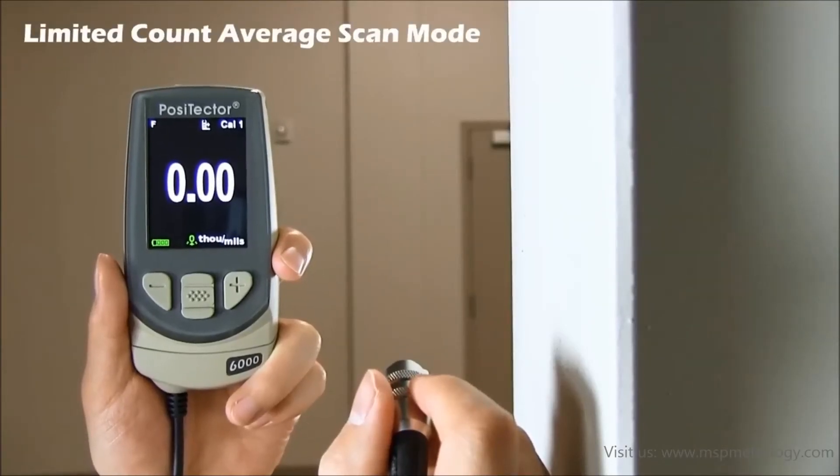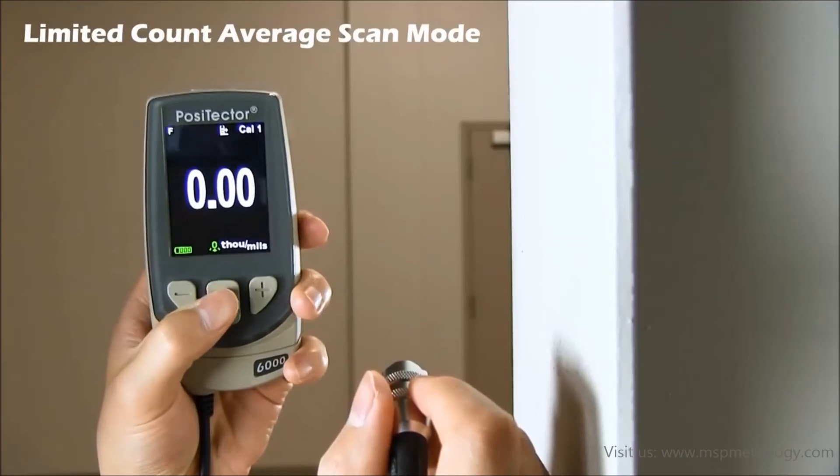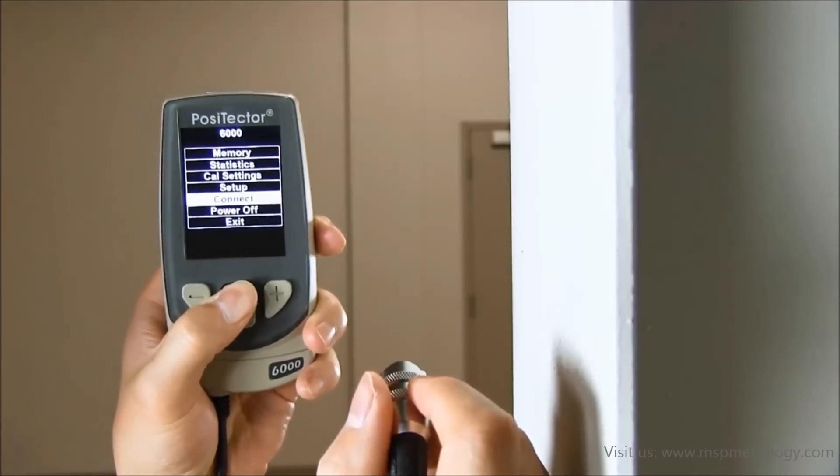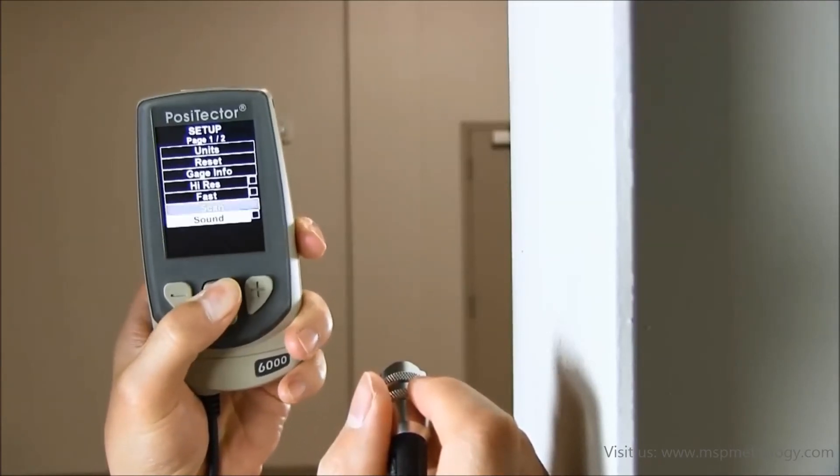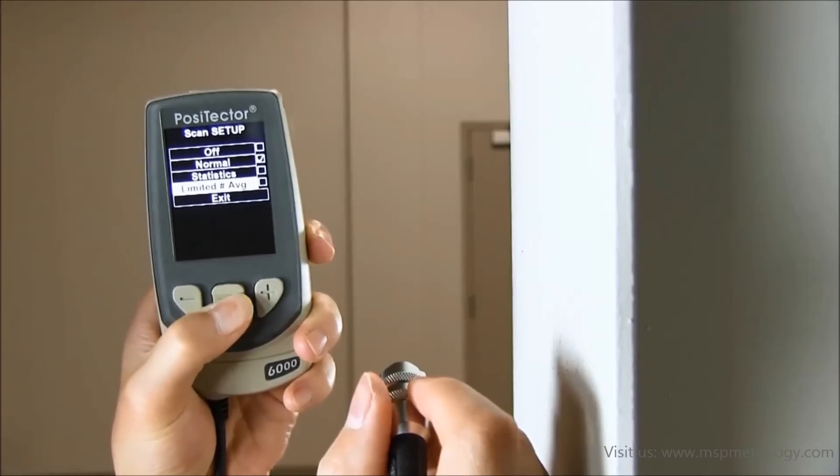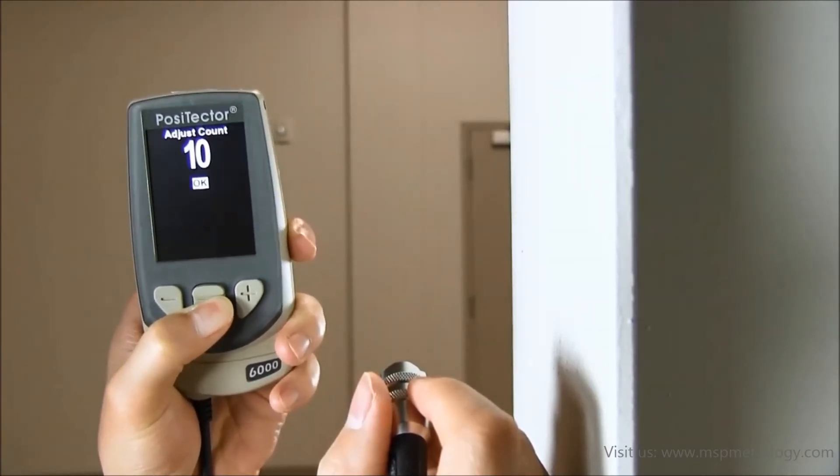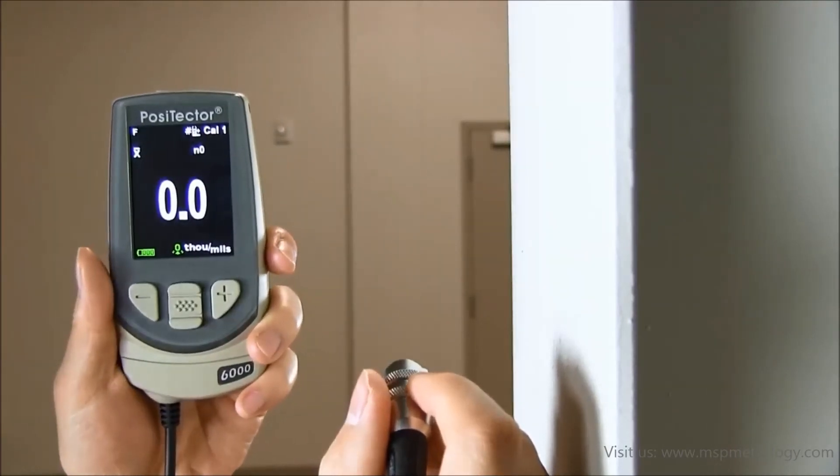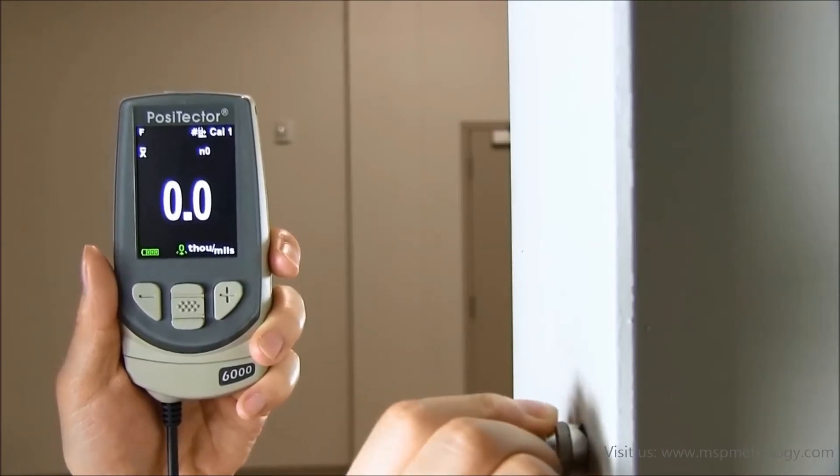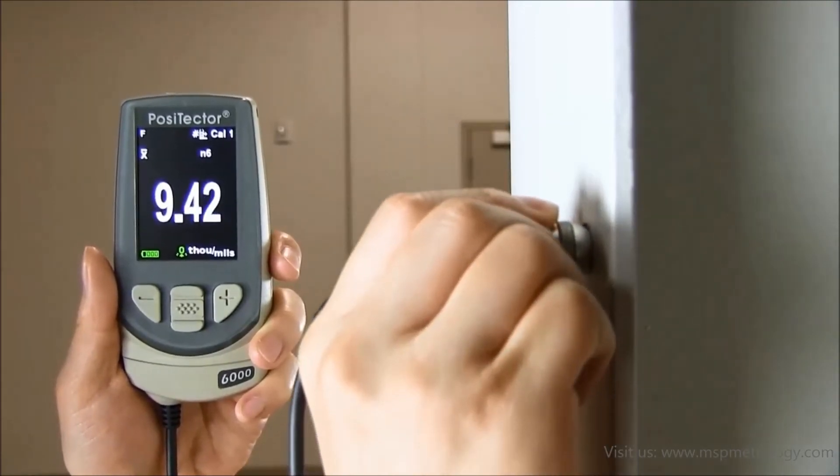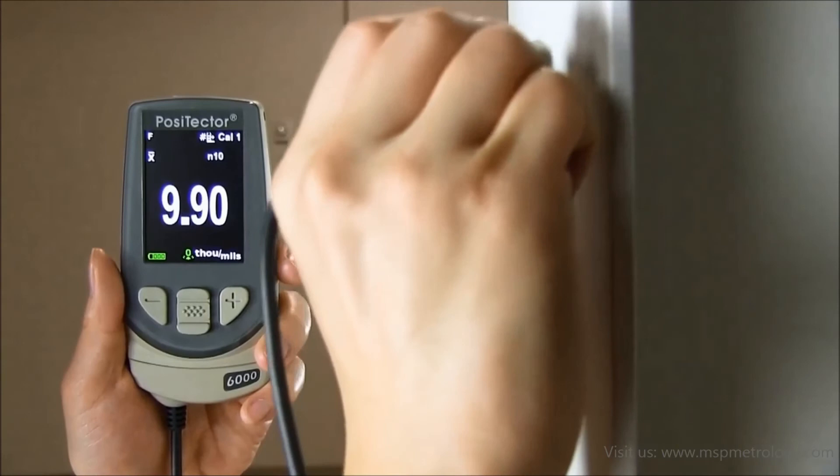In limited count average scan mode, the user is prompted to select a number of readings per scan. Each time the probe is placed on the surface, the selected number of readings is taken. The average is displayed on the screen and saved into memory if enabled. Like statistics scan mode, the individual readings aren't displayed or saved into memory.